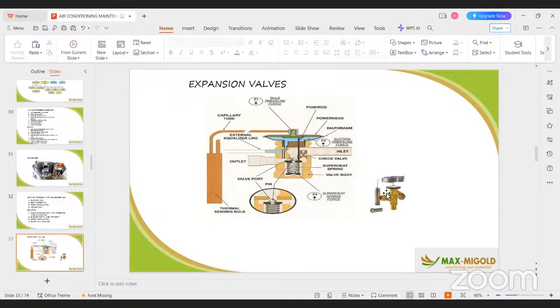But there's a problem. What is the problem? During installation, particles of carbon will drop inside this thin pipe. And once they drop inside this thin pipe, with prolonged quantity of this dirt, they can actually block these small pipes. And because of that, the refrigerant will not go through. And if the refrigerant does not go through, no cooling will be supplied to your building or through the AC. So you need to ensure that this is free of any dirt.